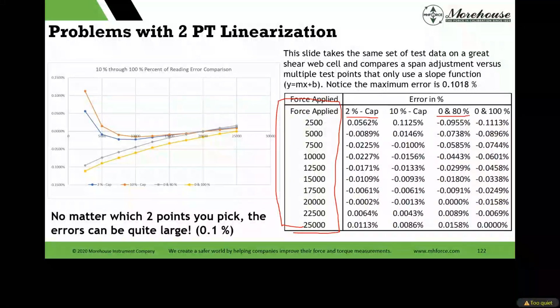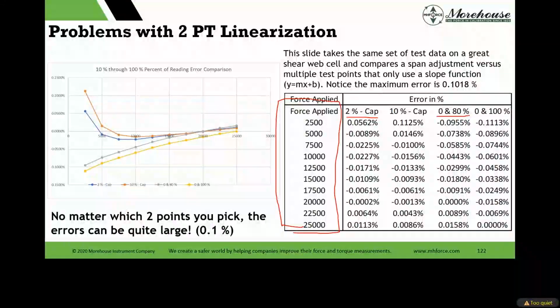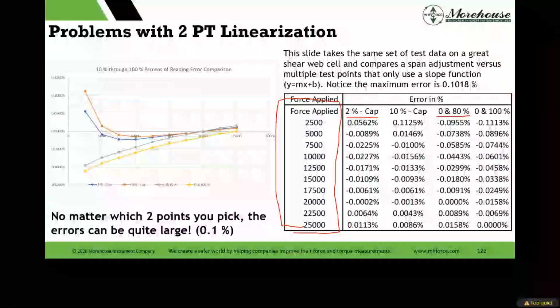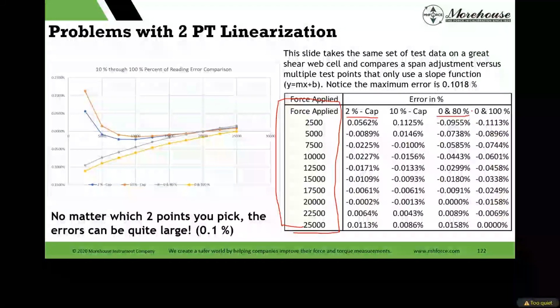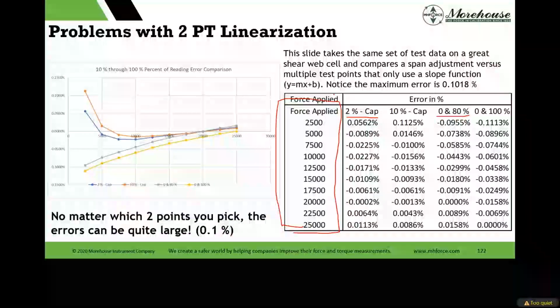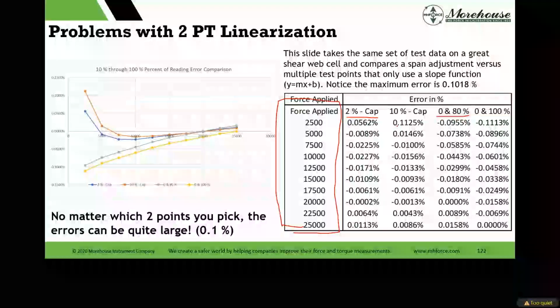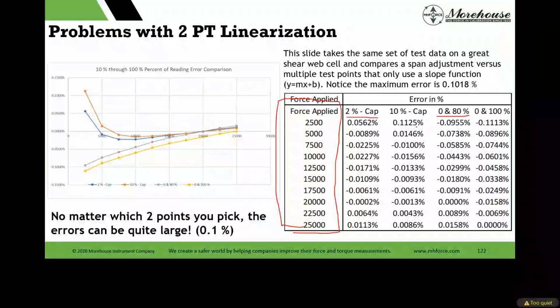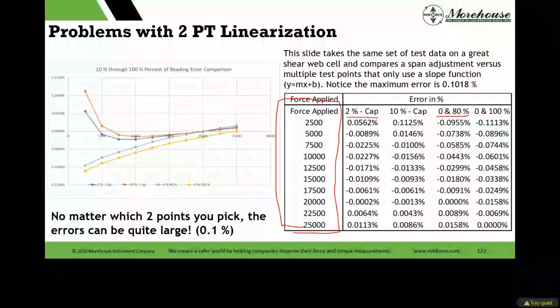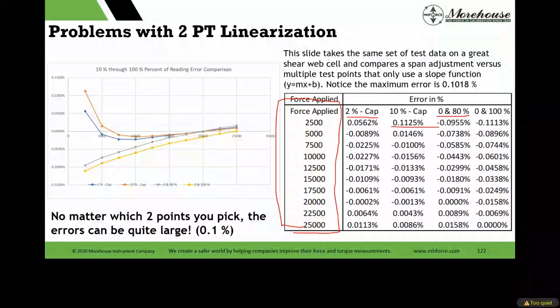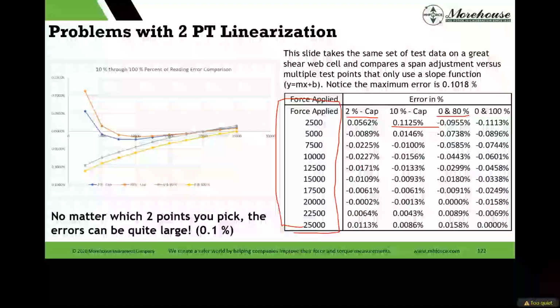Anyway, back to our specifications, nonlinearity. I'm trying to span this load cell at 2 points, and my load cell specification sheet said my nonlinearity is better than 0.2. So if I hook this up to TEDS and do these points, should it not be better than 0.2? Well, this is one of those 0.2 load cells. And if we look at all the points, our best series seems to be this 10% in capacity, which is generally 0.2, but 2,500 we didn't get in there. So something's going on mathematically, and in this cell, an S-beam could be different because it could have more linear behavior.